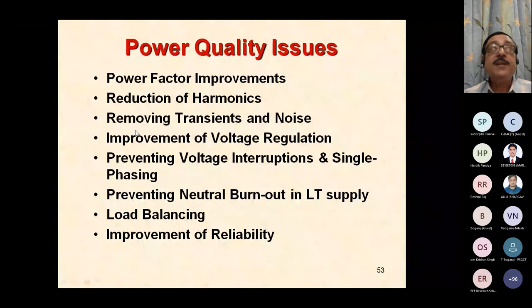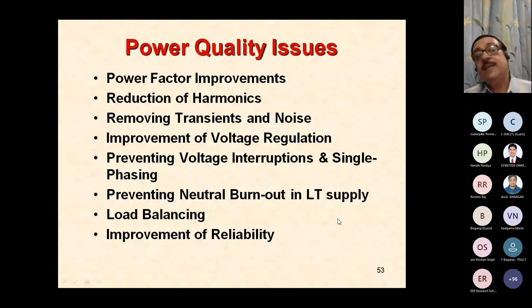Power quality issues involve power factor improvement, reduction of harmonics, removing transients and noise, improvement of voltage regulation, preventing voltage interruptions and single phasing, preventing neutral burnout in LT supply. This is one of the biggest problems because we consider that in LT, systems should be balanced. So there was a provision earlier to supply power through so-called 3.5 core cable. The half core means the neutral cross section used to be 50% of that of the line, assuming that the load is going to be balanced and there would not be significant current in the neutral.